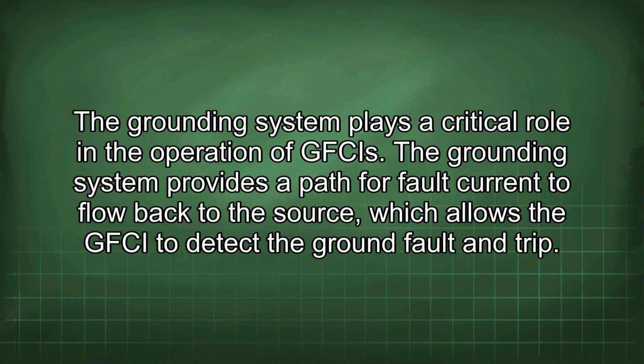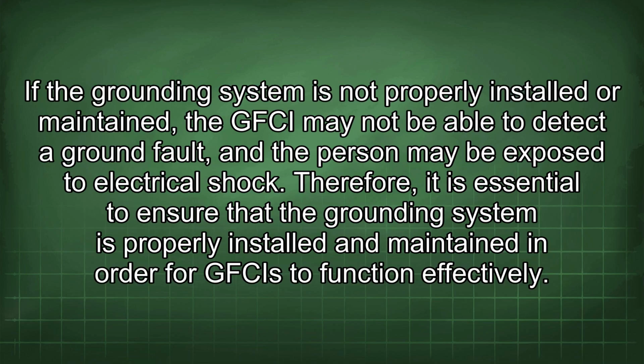The grounding system plays a critical role in the operation of GFCIs. The grounding system provides a path for fault current to flow back to the source, which allows the GFCI to detect the ground fault and trip. If the grounding system is not properly installed or maintained, the GFCI may not be able to detect a ground fault, and the person may be exposed to electrical shock. Therefore, it is essential to ensure that the grounding system is properly installed and maintained in order for GFCIs to function effectively.